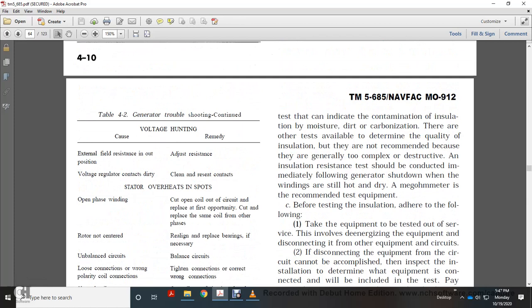There are other tests available to determine the quality of the insulation. They are not recommended because they are generally destructive to the insulation. The insulation resistance test should be conducted immediately after the generator is shut down, with the windings still hot and dry. Megohmmeters are recommended as the test equipment before testing insulation.